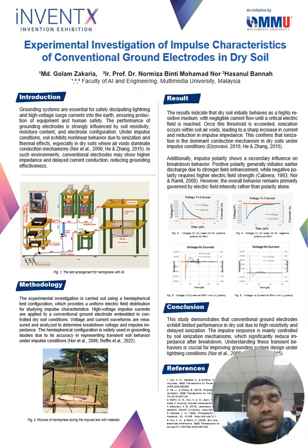Second thing, when the voltage reached around 50 or 55 kV, current inception occurred. This indicates the onset of soil ionization, mainly occurring in air voids between particles. Also, you can see here the effect of polarity shows very weak polarity dependence.